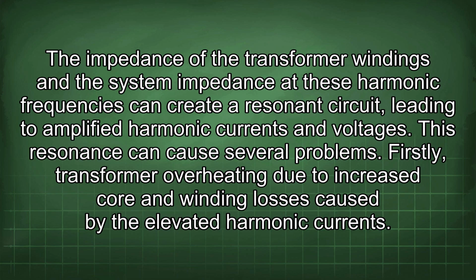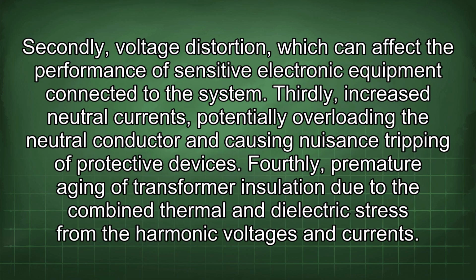This resonance can cause several problems. Firstly, transformer overheating due to increased core and winding losses caused by the elevated harmonic currents. Secondly, voltage distortion, which can affect the performance of sensitive electronic equipment connected to the system. Thirdly, increased neutral currents, potentially overloading the neutral conductor and causing nuisance tripping of protective devices. Fourthly, premature aging of transformer insulation due to the combined thermal and dielectric stress from the harmonic voltages and currents.